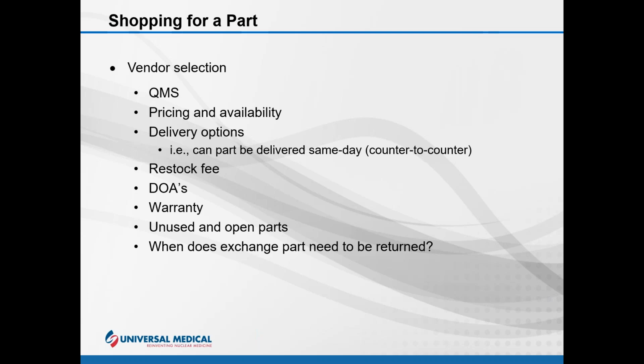Also, when needed, a hero kit can be an option. This will typically include all the parts necessary for an intermittent problem. Let's say after speaking with tech support, the system was diagnosed with an acquisition issue, but they weren't able to, let's say, pinpoint the problem. So all of the boards associated with the acquisition side can be sent to try and diagnose the problem quicker. This can minimize downtime and shipping costs. And restock fees typically will only be charged for the parts that have been opened and used for testing.